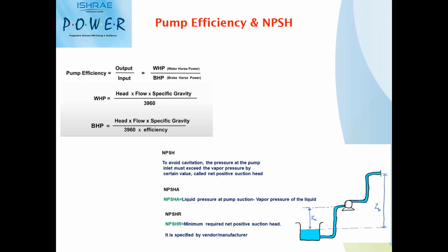So particularly whenever pumps are being designed, the pump should have minimum pressure required on the suction side to function without any cavitation or sucking of air. Basically, cavitation is nothing but the vibration created by the impeller due to sucking of air or vapor, whatever you can say. So whenever a pump is being operated, it should have a minimum suction pressure on the suction of the pump. That value is called NPSH required by the pump, or NPSH-R. This is a design parameter of a pump.